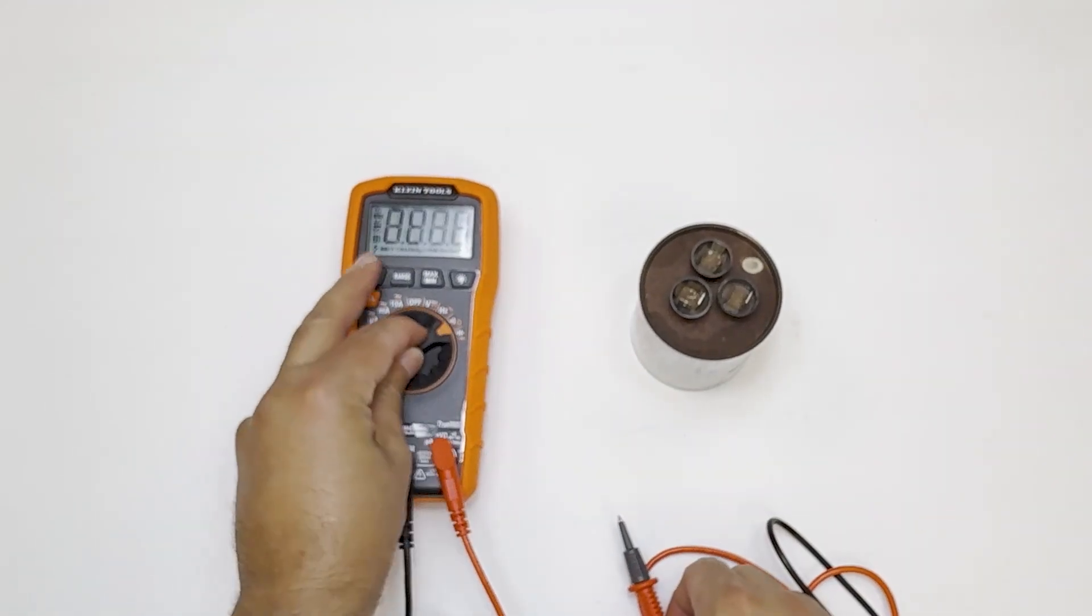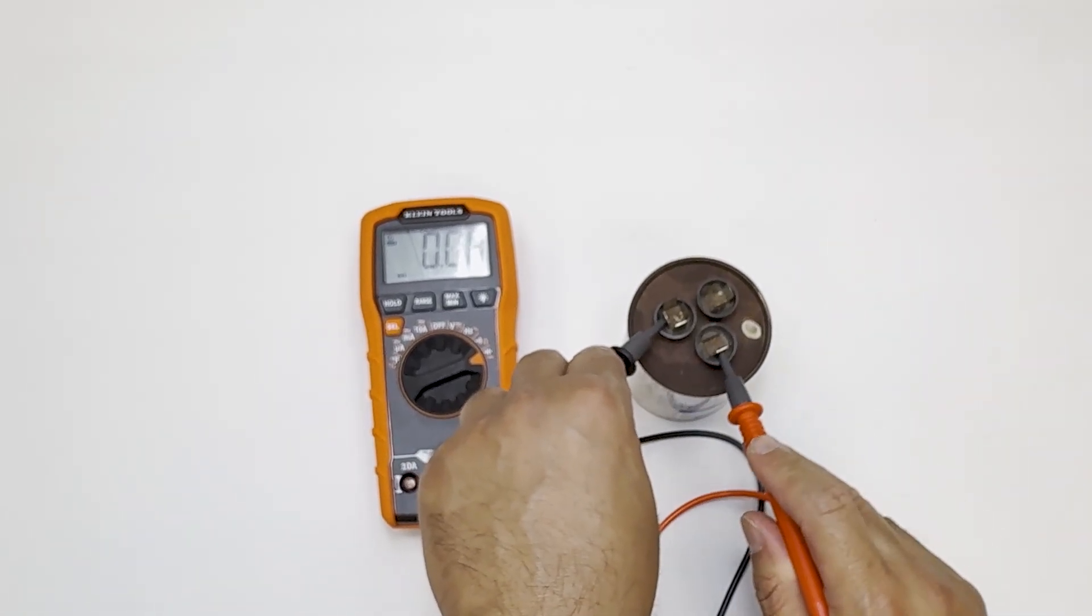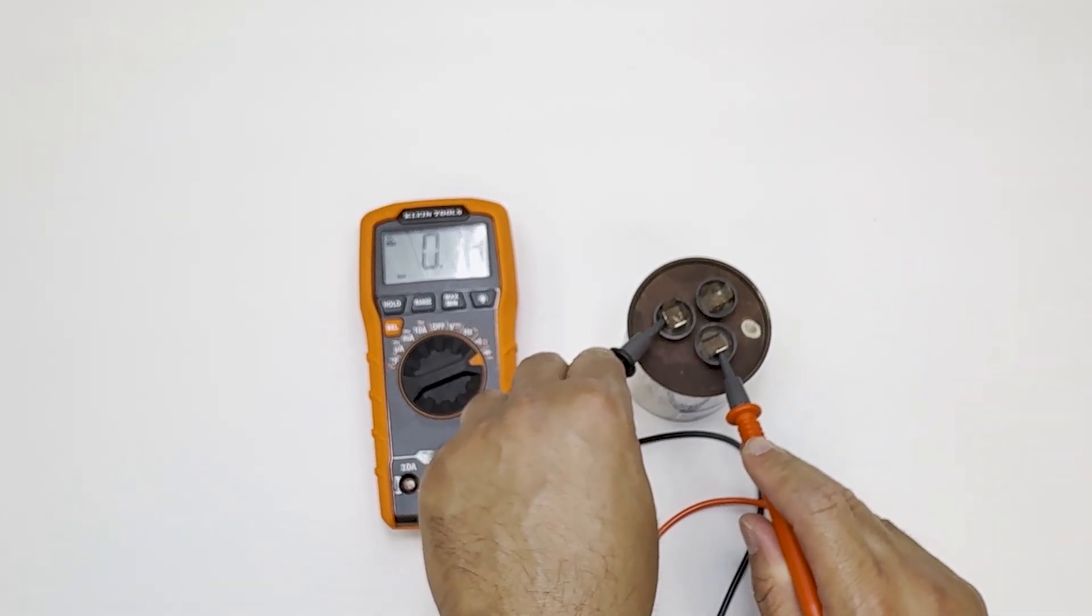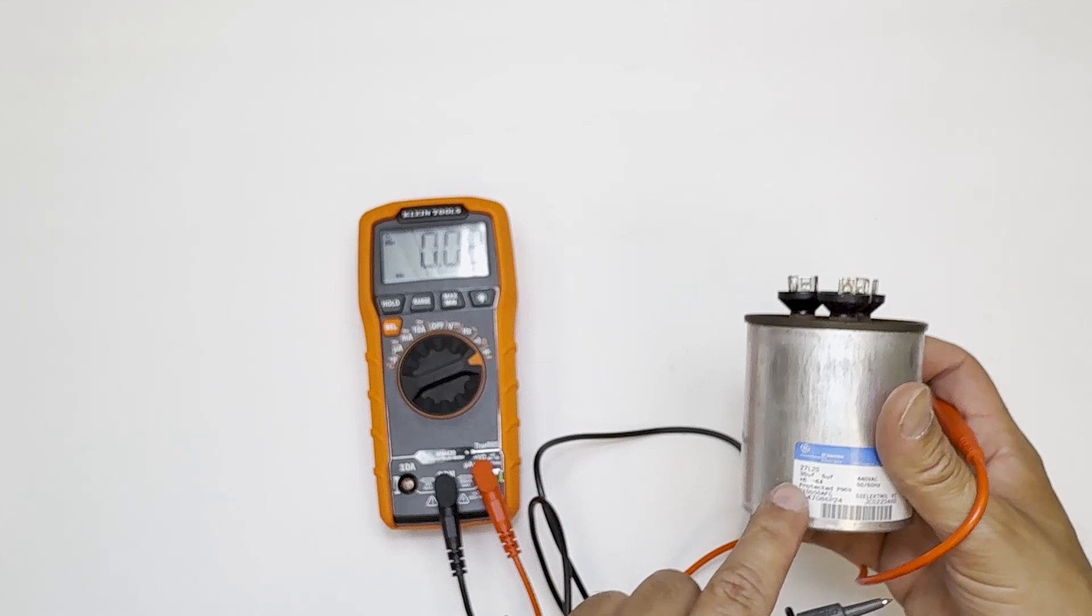So in testing the bad capacitor, C to fan shows 0 microfarads. It should be close to 5, but we're getting nothing, so it's totally bad. So we know for sure this capacitance is bad, even though the fan is supposed to show 5 microfarads.